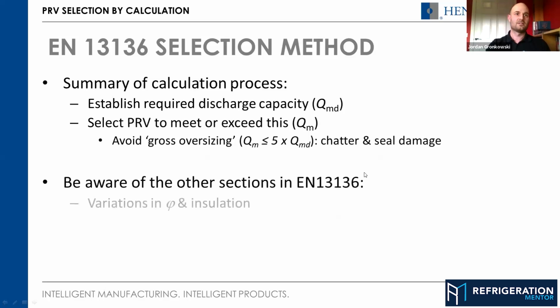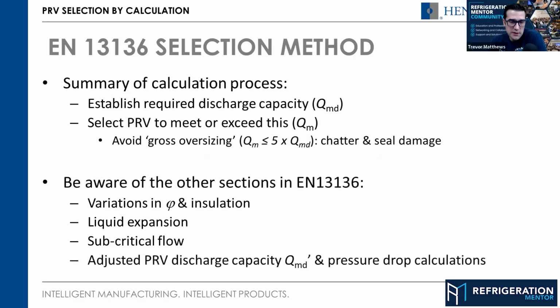Right, where did we get to? Selection method there. Let's get through this. Other sections, we talked about that. So let's get into the liquid section. This is important. We need to make sure that if it's a gas PRV, it's on the gas line, so discharge line or suction line, it's gas. But if it's in the liquid line, you need a different design. And why is that? Is it just because you need more flow because liquid's denser or whatever? Does it need to be bigger?